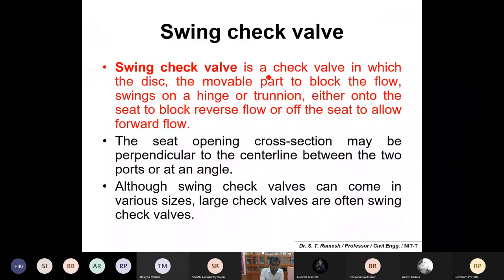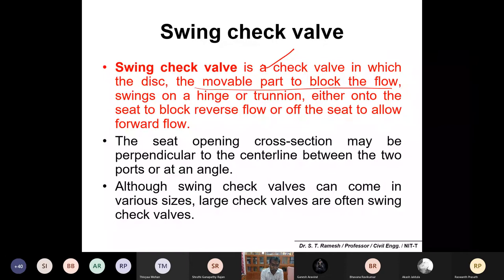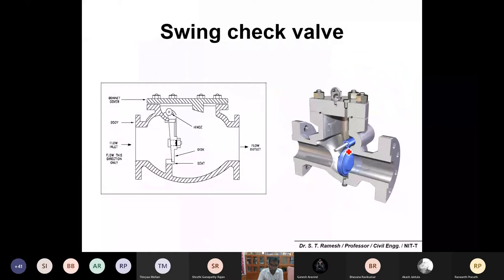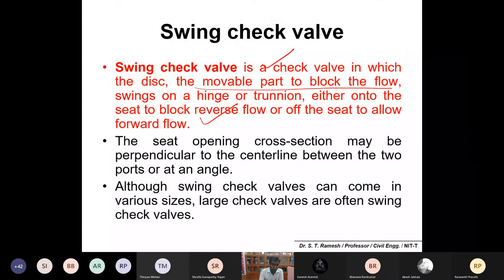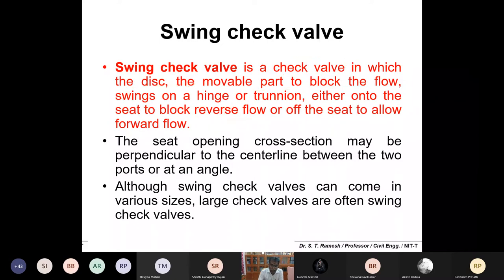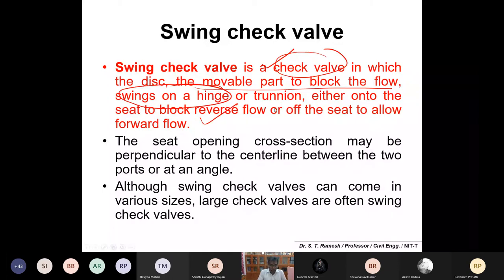The third one is the swing check valve. A swing check valve is a check valve in which the disc — the movable part to block the flow — swings on a hinge or trunnion, either onto a seat to block reverse flow or off the seat to allow forward flow. Instead of being fixed in one position, it is mounted on a swing and opens or closes based on flow direction.